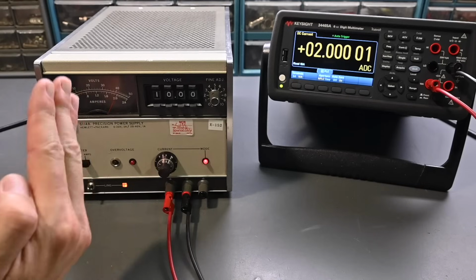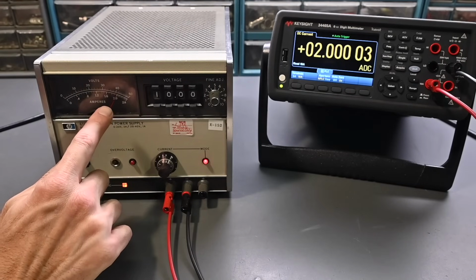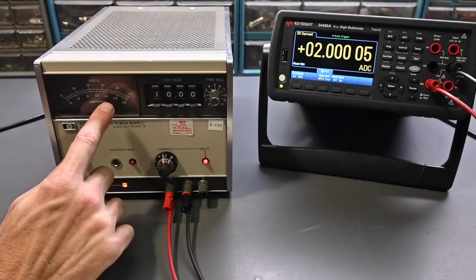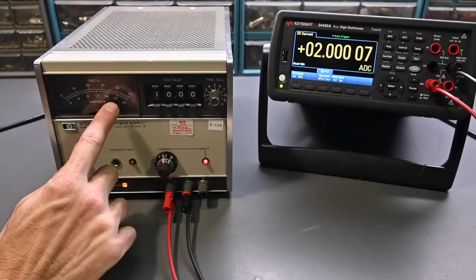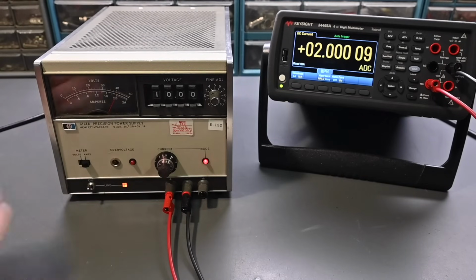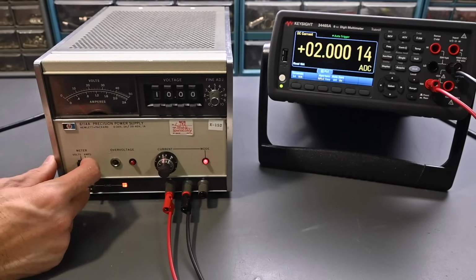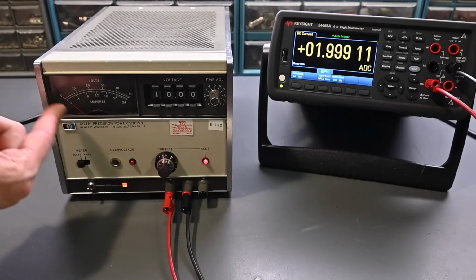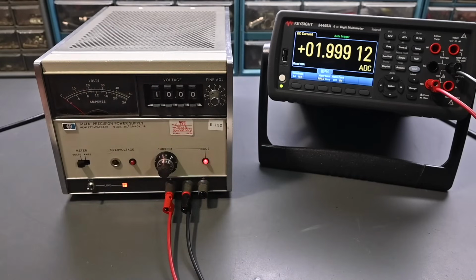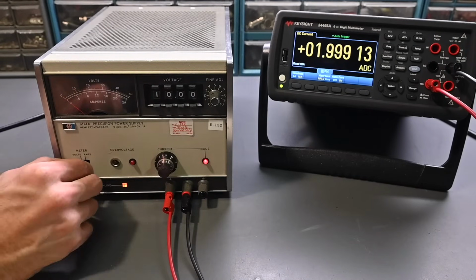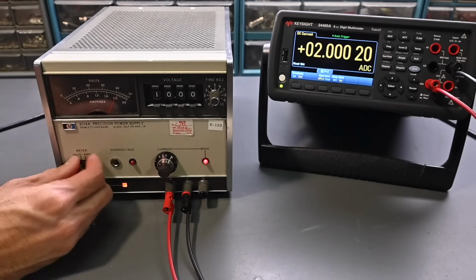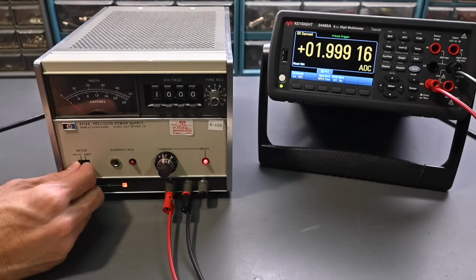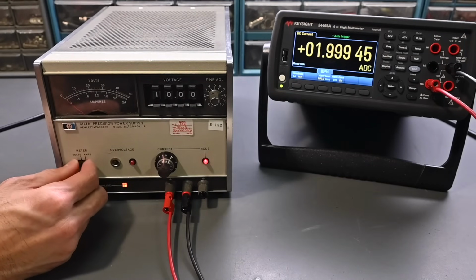And if I look straight on this meter, it's right at the 2.0 tick mark, maybe just a touch under, but very, very close, certainly within reason. I don't think that's any kind of a problem there. But if I go like this and I put this back to voltage, now it's indicating a very low value because it's in constant current mode and the voltage has dropped very low. But if I move this back over again, and of course it's cooperating right now, but it seems to be okay. Let me see if I can do this.